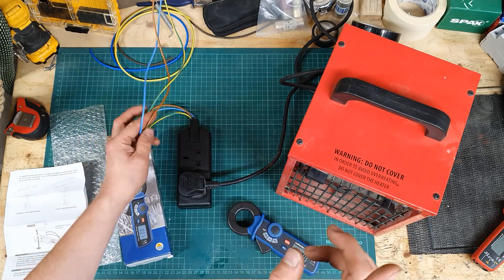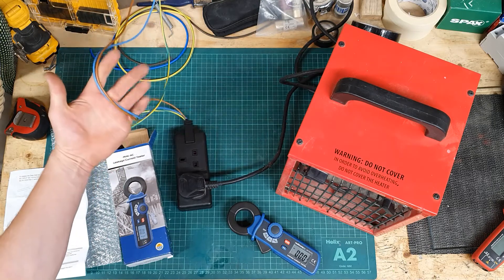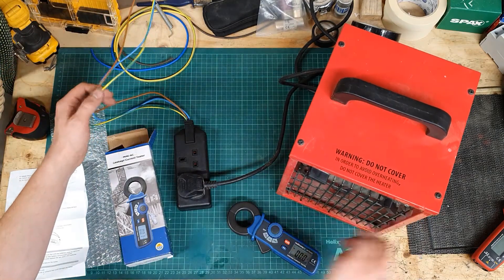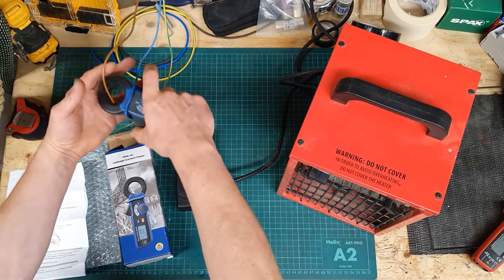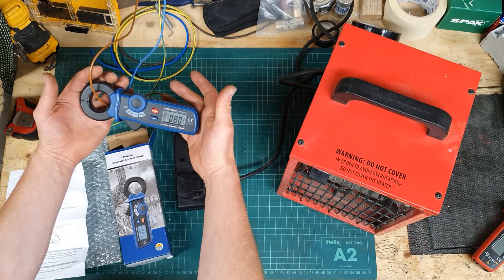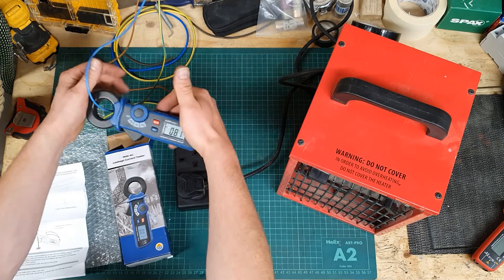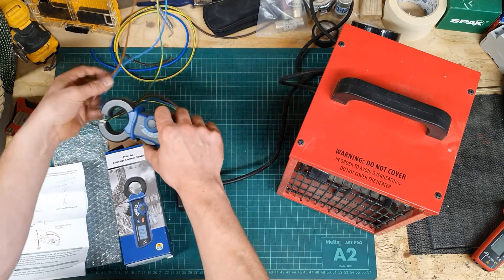The problem I found was when trying to look for the difference between what's going down the line conductor and what's in the neutral. If I switch it on just to get our bearings — it seems to measure load current okay. It's reading around 8 amps, which seems about right, and we have around 8 amps returning in the neutral, although there's a little bit of discrepancy.